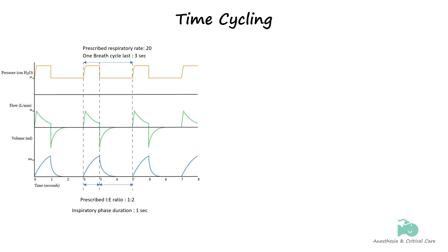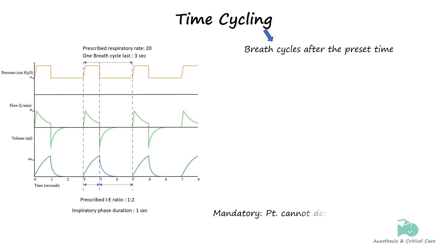A breath is considered time-cycled if the inspiratory phase ends when a predetermined time has elapsed. This is usually a feature of mandatory modes of ventilation. The preset time in time-cycling is determined by the respiratory rate and the inspiratory-to-expiratory ratio set by the clinician.